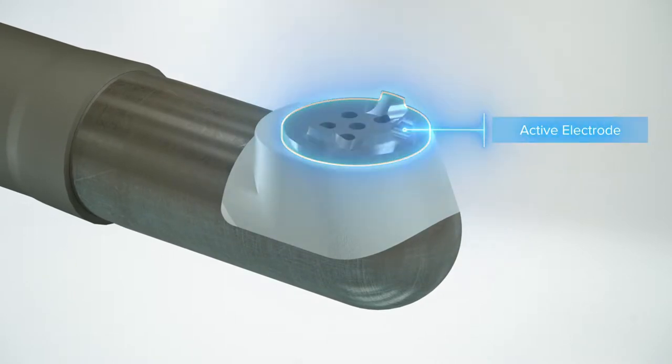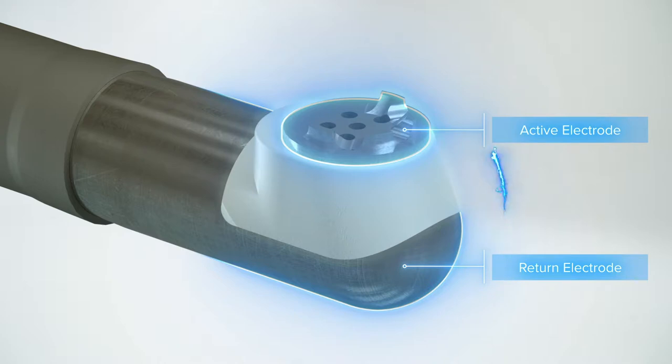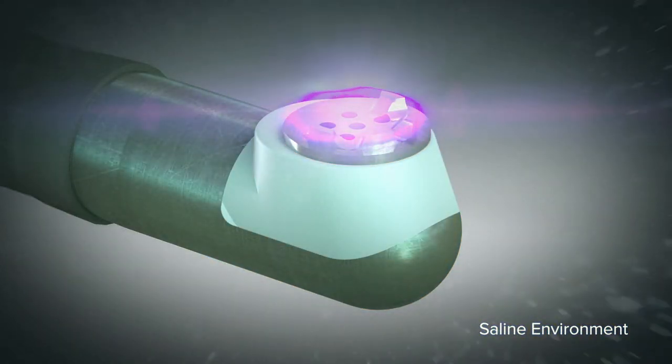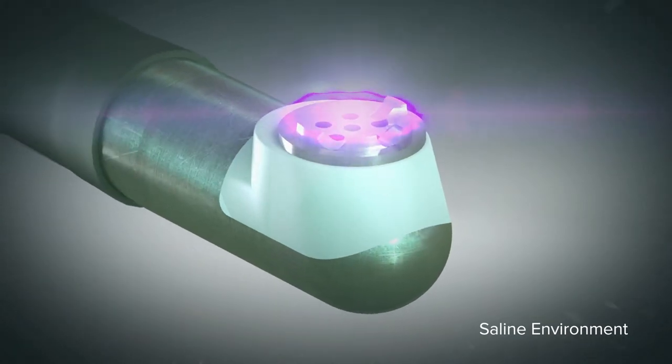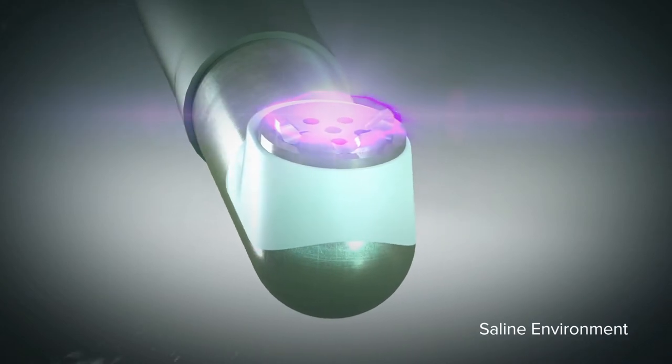The system operates at a specified radio frequency and generates an electrical field at the tip of the device. Electrical energy flows through saline, creating a chemical reaction that generates a high-density energy field at the tip of the probe. The ultra-thin plasma layer contains energized particles that have sufficient energy to break organic molecular bonds.